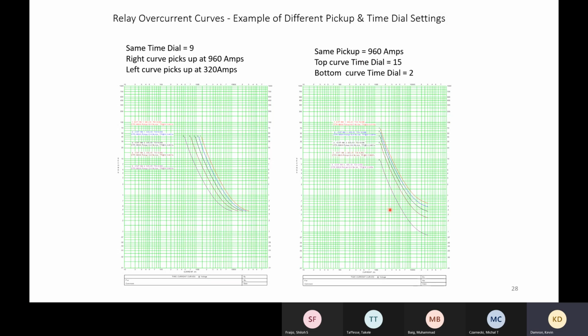So if you ever want to have a lot of fun and spend some time in protection, an interesting thing here is this, showing the effect of the time dial on the pickup. Here we had the same time dial 9, and it goes anywhere from a pickup of 320 amps to a pickup of 960 amps. If you look at this, curve 1 is way over here. It stops here. Well, what they do is they draw a dashed line up. This line, number 1, would come all the way up to 960. So it comes up just to here.